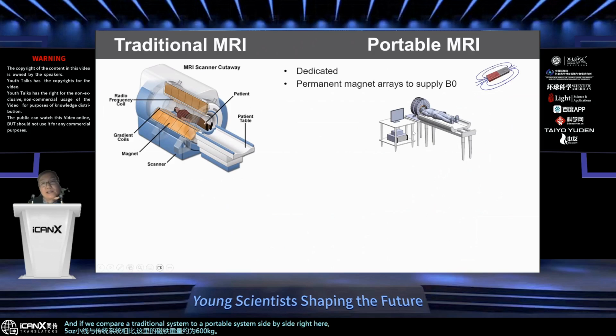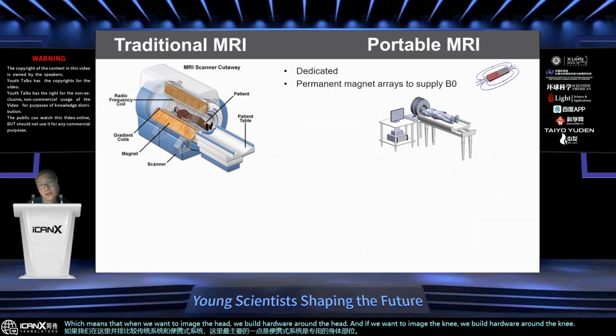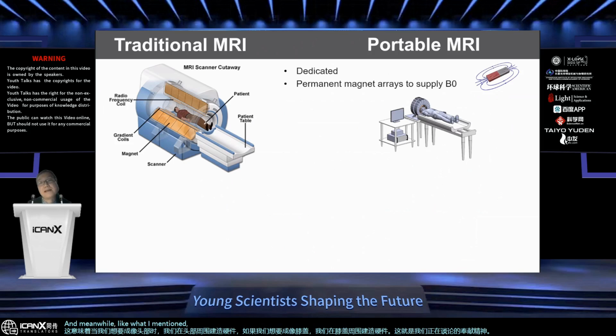And if we compare a traditional system to a portable system side by side, one main thing is that the portable system is body part dedicated, which means that when we want to image the head, we build hardware around the head. And if we want to image the knee, we build hardware around the knee. That's the dedication we're talking about here. And meanwhile, like I mentioned just now, permanent magnets are used, so it carries its own energy.